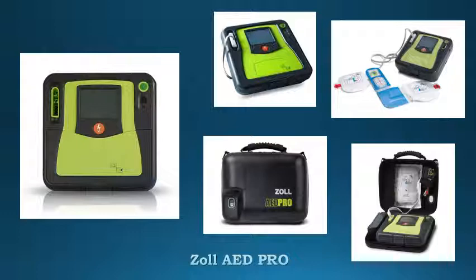Zoll AED PRO features superior AED design and rubber over-molds are built to withstand harsh environments. Real CPR helps monitor depth and rate of chest compression during CPR using Zoll's unique one-piece CPR-D pad. See-through CPR allows rescuers to view a patient's underlying ECG rhythm while performing CPR.